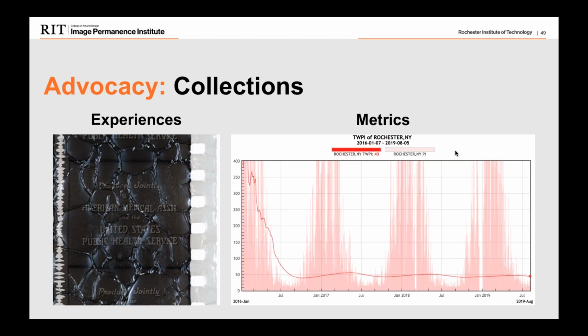Finally, a question about why we worry about relative humidity in winter and dew point in summer. Dew point is one of the factors that controls the other two, and it indicates when dehumidification has to occur. We look at relative humidity more in winter because when we see low RH levels in a collection space, that's when we look at humidification. Part of the reason we look at these parameters differently by season has to do with what type of control we're employing - dehumidification or humidification.